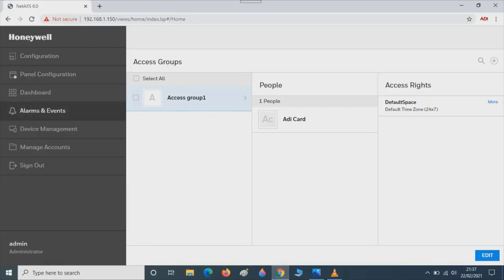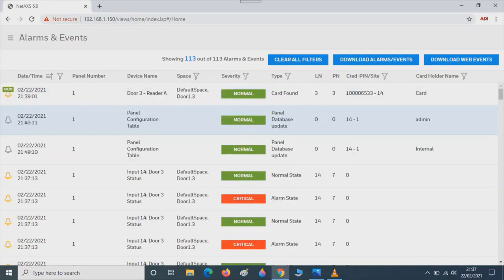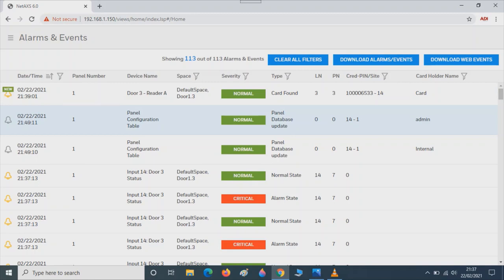We'll go to the alarm and event menu. Here you can see all the live events happening. Last event was me updating the database. Next, I'm going to present a card. Card found. You can see it's normal, so it's not an alarm. That means access was granted.